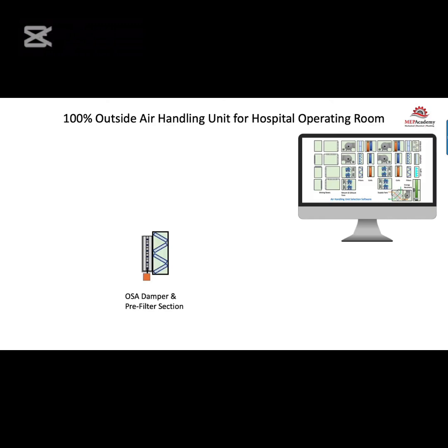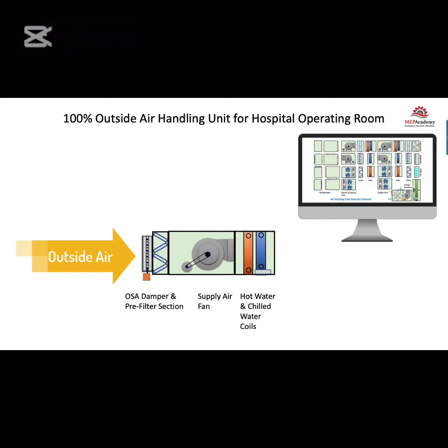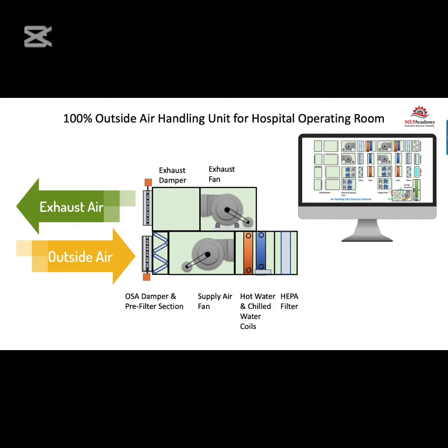First thing we'll need is the inlet from the outdoors. We'll have a damper with an actuator, and the first section will be our pre-filter section to clean the air that's coming in. And then we'll have our supply fan. This is what will suck the air from the outdoors and push the air into the operating room. Then we'll have a hot water and chilled water coil to temper the air. And finally, we'll have a HEPA filter to clean the air, because there's additional requirements for the operating room. Since you're cutting people open, the air has to be super clean. And then on the exhaust side, we need an exhaust damper and an exhaust fan to take the air from the room and exhaust it out.